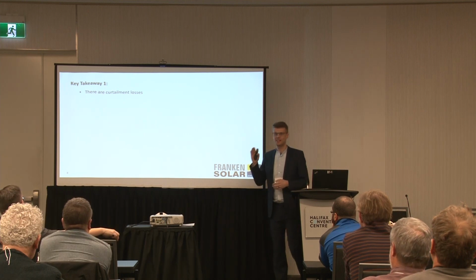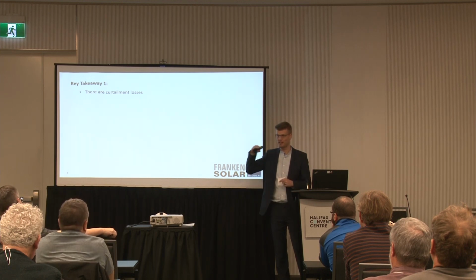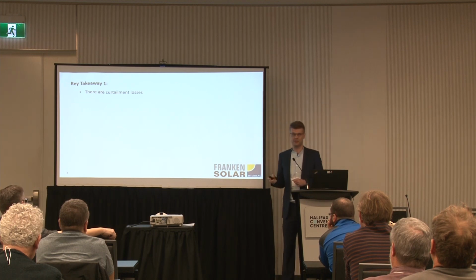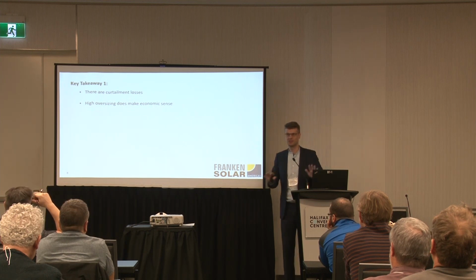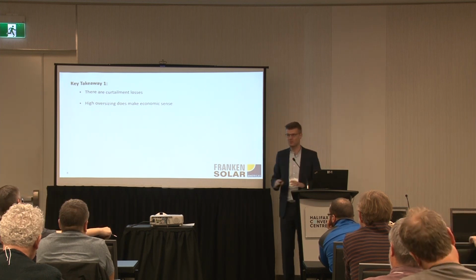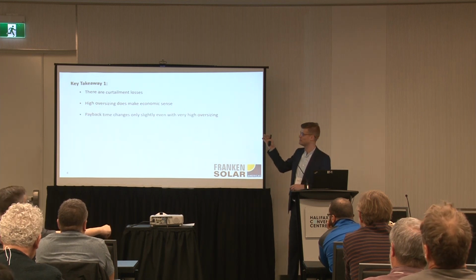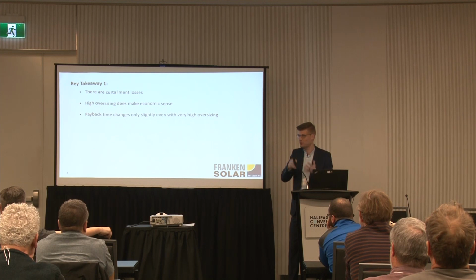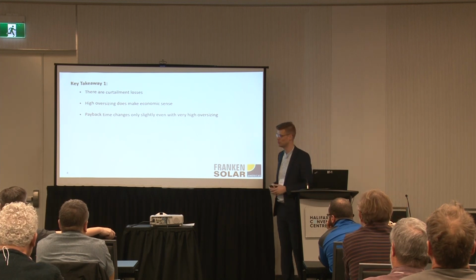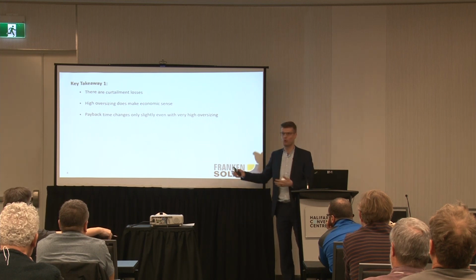The number one message is, yes, there will be curtailment losses. It's not perfect. If you have high oversizing, you will be operating at the 10 kilowatt limit and you will lose energy. The other message is the loss of energy is actually not that great. And high oversizing makes economic sense when you put the physical installation and the yield of the system and the economics of the system together. And then from a customer perspective, the payback time doesn't really change a lot, no matter if you operate at 1.3 or 1.4, or even a 1.8 to 1 ratio, which for a lot of installers in the first place seems a little bit weird to go with 1.8 to 1.